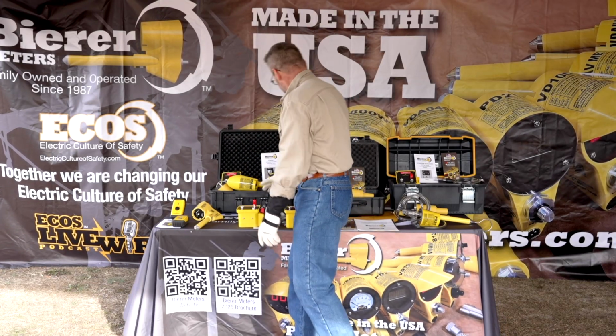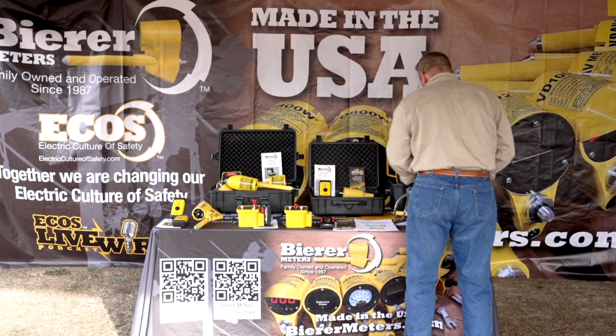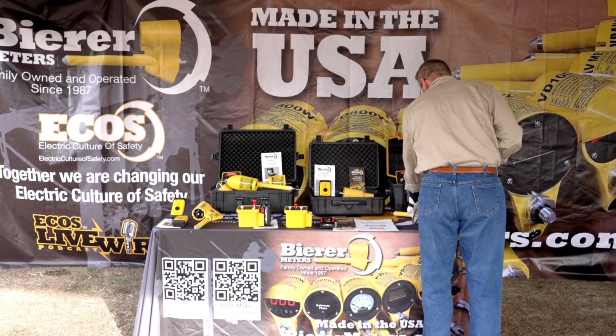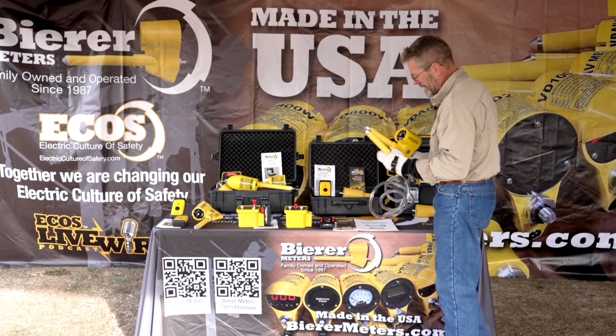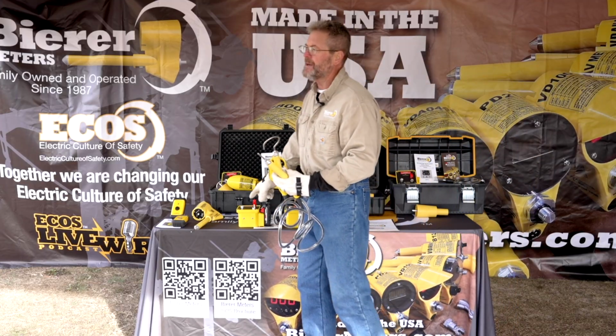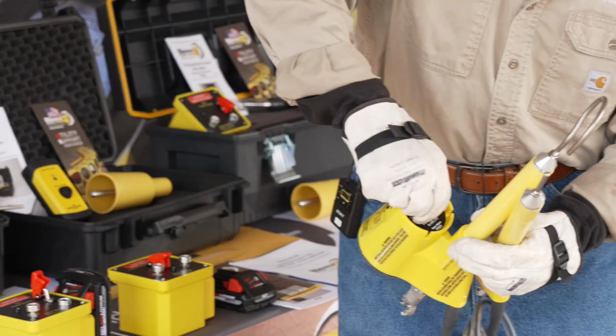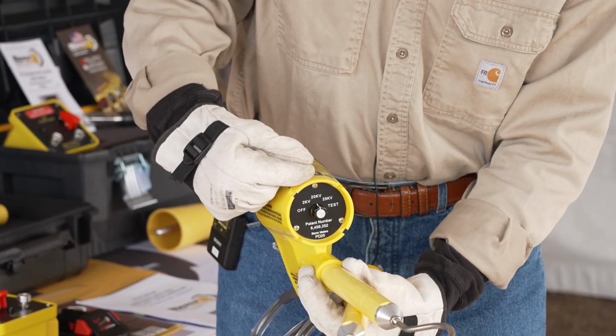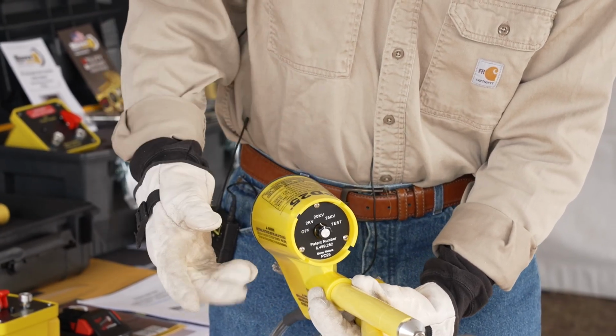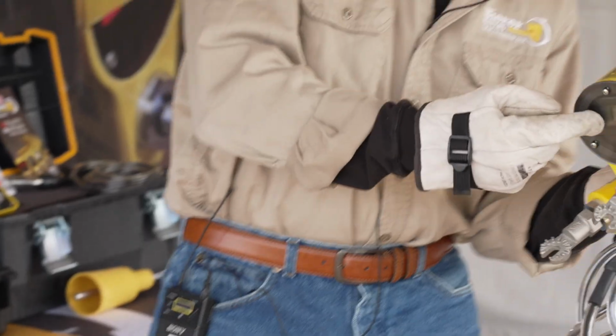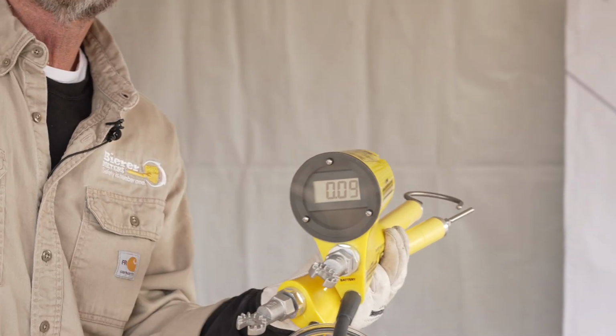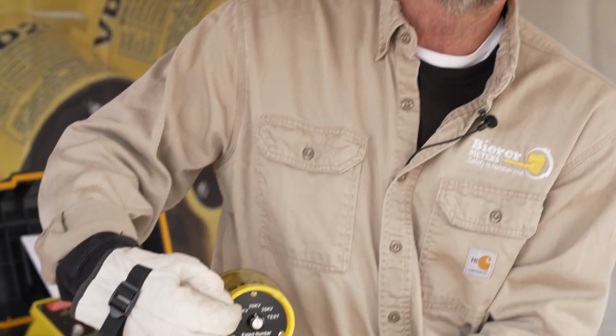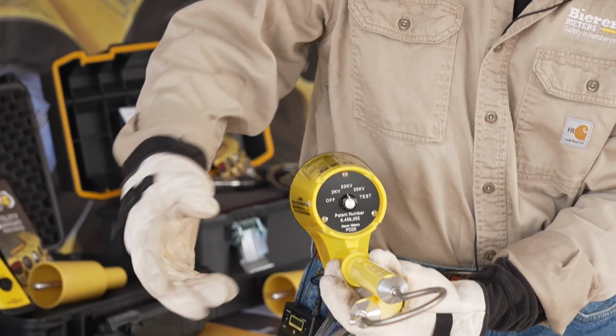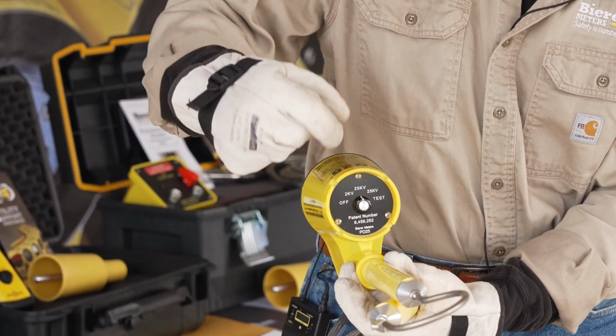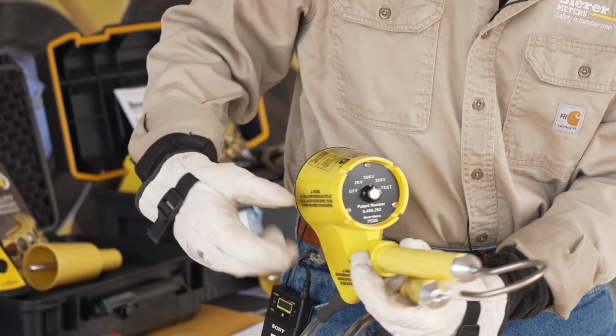Okay. We're going to take our PD25, because that's a 3 kV power supply. We're going to go up here to 20 kV. 2 kV would be an overload. We'll see a number 1 on the screen if it was overload, because it's higher than the 2 kV position. It doesn't hurt the tool if it's overloaded. The tool's just telling you your positioning is incorrect. So check your setting. So we have it on 20 kV.